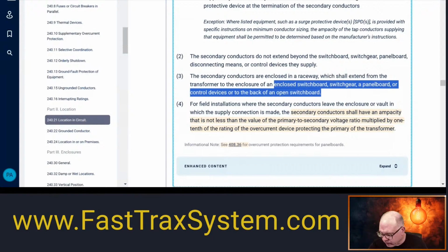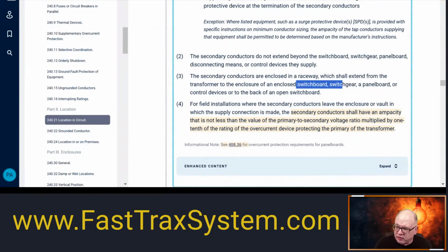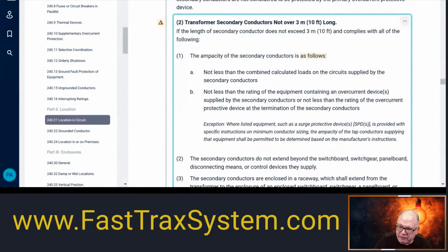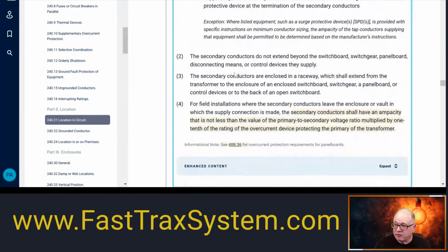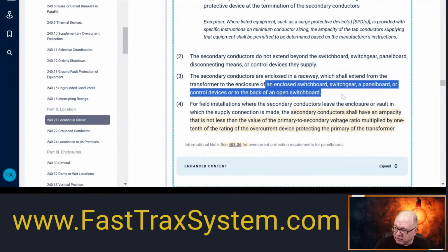Okay. But if you wanted to play the semantics game, and have some inspectors say, well, it doesn't say disconnecting means, and I'm coming out of the transformer and I'm hitting a disconnecting means, so it doesn't have to be in a raceway. I would think that he would say to you, well, look, if you're not following this entire rule, then I'm not going to let you use the 10-foot rule. And since they can only be enclosed in a raceway, the secondary conductors, then I'd rather not get in that argument with the inspector, because then he might say, well, I see what it says here, but here it doesn't say anything about that raceway going into a disconnecting means. So guess what? I'm not going to let you do it.